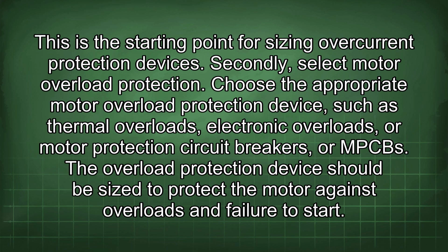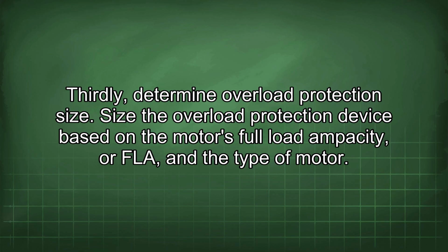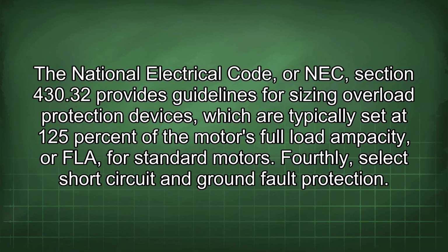The overload protection device should be sized to protect the motor against overloads and failure to start. Thirdly, determine overload protection size. Size the overload protection device based on the motor's full load ampacity, or FLA, and the type of motor. The National Electrical Code, or NEC, Section 430.32 provides guidelines for sizing overload protection devices, which are typically set at 125% of the motor's full load ampacity, or FLA, for standard motors.